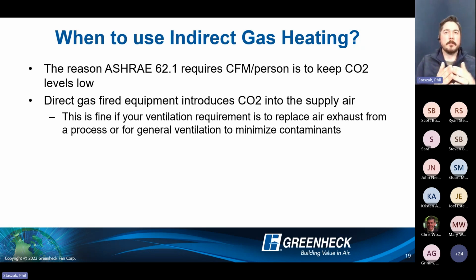So remember that if you're burning gas, it's the most effective form of gas heating in the industry, because you have literally 0-degree entering air coming across that open flame burner, heavily diluted by the outside air, with minimal amounts of CO2, CO, and the scary stuff coming into that space. But remember the general application again. Yes, we're bringing in all thermal properties, which is the advantage. We are bringing in a slight amount of the stuff you don't want to be breathing in, but remember where it's going. It's coming in for process exhaust. So it's coming in, kitchen is a great example, hits the chef in the back of the neck, and then it gets exhausted right back outside.